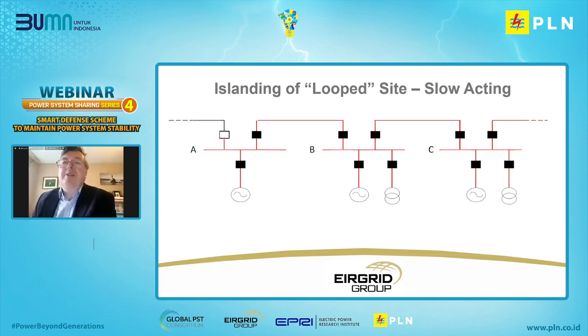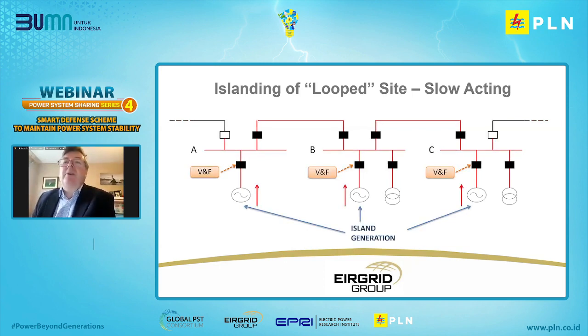Okay, so next slide, please. So this is an example of the slow acting one. So one of the lines into station A has tripped, and one of the lines into station C has tripped. So now essentially stations A, B, and C are islanded, but we're not able to get the breaker status from the necessary remote ends. So now we're relying on voltage and frequency protection to kick in. So there's islanded generation there in 3 stations, and voltage and frequency protection is active. So next slide, please.